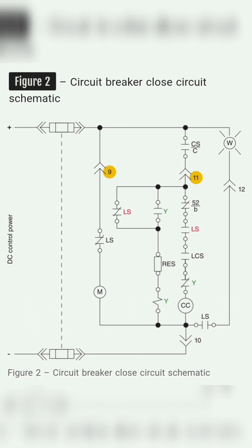With the breaker open, contact 52B is closed. The 52B contact is an auxiliary contact that simply mirrors breaker status — it is closed when the breaker is open, and open when the breaker is closed. The normally open spring charged limit switch LS contact, located below the 52B contact, is closed when the closing spring is charged. This contact ensures that mechanical force is available to close the breaker. Downstream of the 52B contact is the latch check switch LCS, which enables instantaneous reclosing by confirming the mechanical mechanism has been reset after a breaker trip.